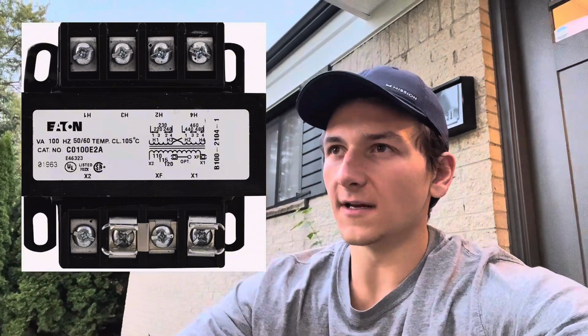Alrighty folks, today I want to talk about the importance of bonding the neutrals of control transformers. Now, this idea came to me because I was thinking back to my early days of troubleshooting and trying to diagnose faulted machines, and I remember getting hung up and stuck on reading weird voltages to ground. Like I would test from hot to ground and I was getting 70 volts, and neutral to ground I was getting something like 30 or 40 volts when I was expecting 120 volts to ground from my hot and 0 volts to my neutral. Now, this was simply caused by the lack of a bonding jumper between neutral and ground.